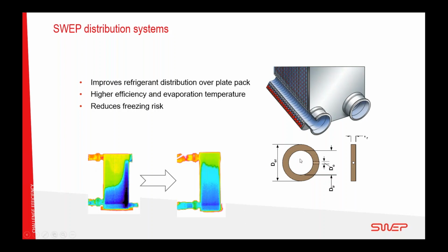this distribution system has to be able to solve the problem of the gas wanting to take a shortcut. If the distribution system is not there or not well designed, the refrigerant gas, when it comes in, wants to take a shortcut and finds the fastest way through the heat exchanger, as you can see here. So the dark blue is the refrigerant liquid that has to evaporate and leave a lot of latent energy inside the heat exchanger. And all this area here is just the gas running away and taking the shortcut out.